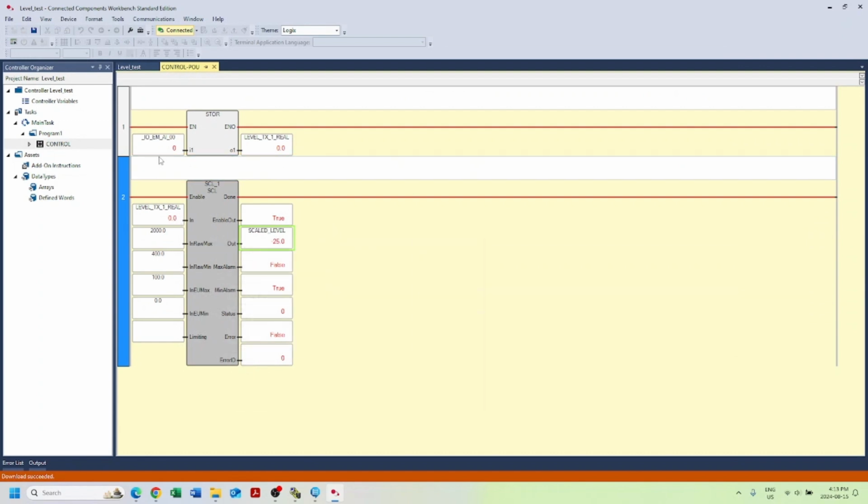So now I've got a bunch of numbers in here, but I have nothing. As you can see, we're about minus 25%, as you'd see in a multimeter, because we're at 0 and 400 is the minimum. So I'm going to go ahead and power up the loop to my process meter. Okay. And in doing that, we're going to stitch this in here, and we're going to simulate an output.